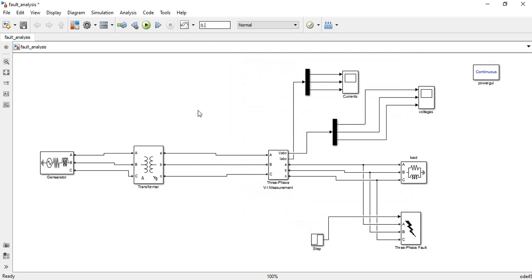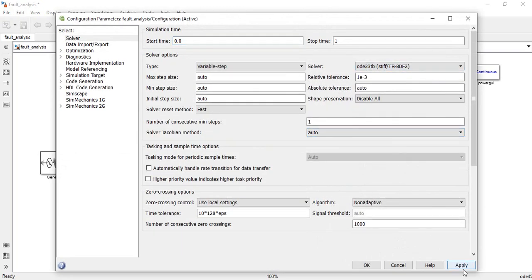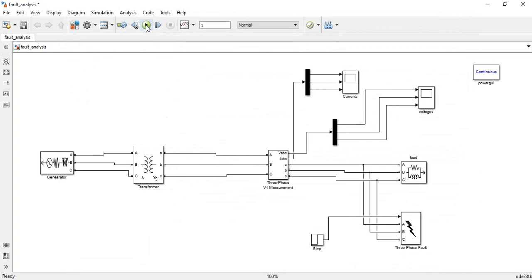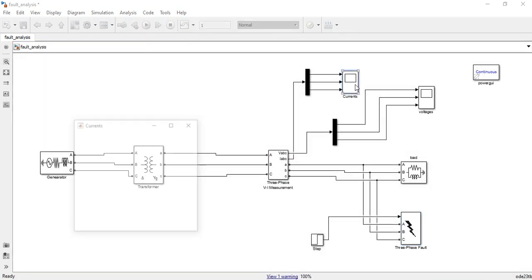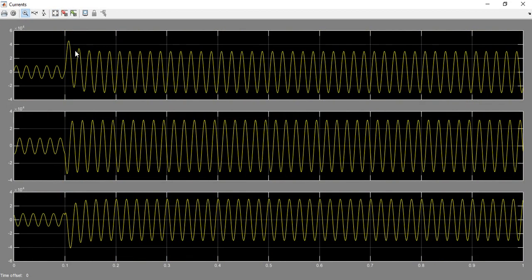Set the simulation time to 1 second and go to Simulation > Model Configuration Parameters to select the appropriate solver. Run the model. For the three-phase to ground fault (symmetrical fault), observe the currents: we see three-phase balanced currents before the fault. At 0.1 seconds, the fault occurs and all three-phase currents increase significantly, as expected for a symmetrical three-phase to ground fault.